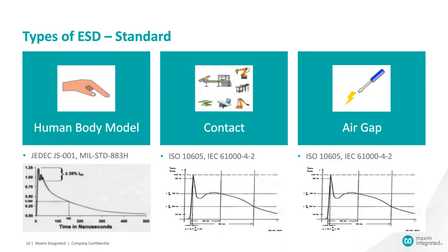The different types of ESD, as I laid out here, are the human body model, the contact where it's actually equipment touching equipment, and then air gap, where that discharge occurs when you're not necessarily touching. The spec calls for about 1 centimeter distance. You can see that they all share very similar waveforms, right? That is a measurement of current versus time.